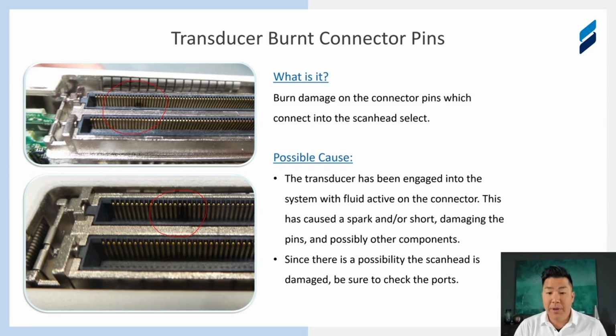What is likely to happen here is we've seen that some light fluid, typically a little bit of gel on accident, maybe some cleaner, accidentally got on the electronics of the probes. Don't use fluids on this part of the transducer to decontaminate them. Very bad idea. It can cause these kinds of things: there's a spark and an arc here, and we commonly see it when there's a little bit of fluid there, and bam. That fluid will be right across two pins right here. Here's multiple pins actually, and those two pins will short.